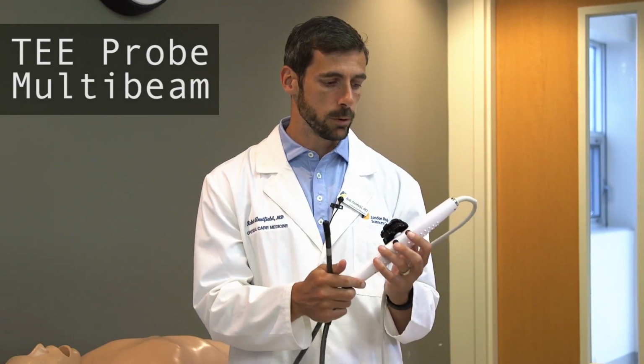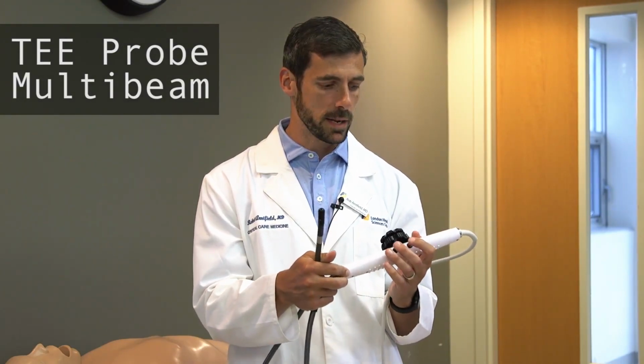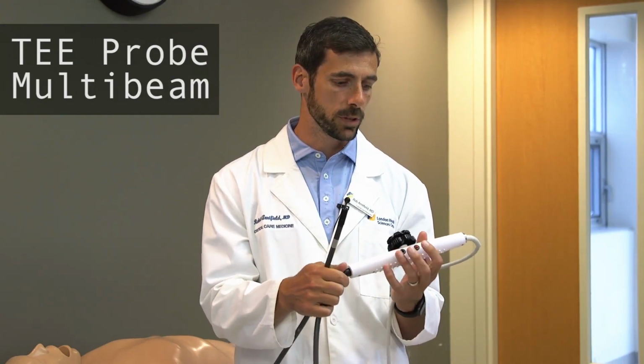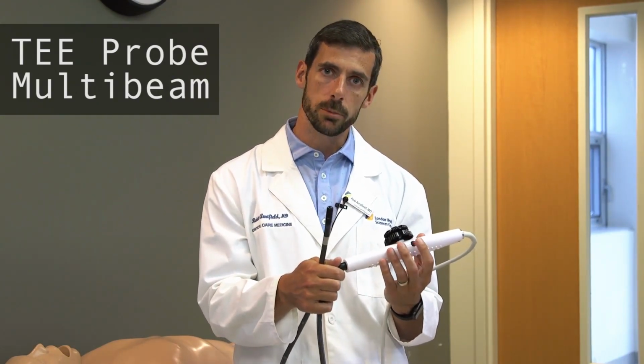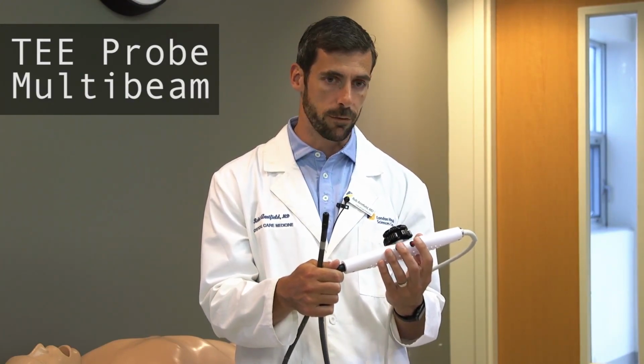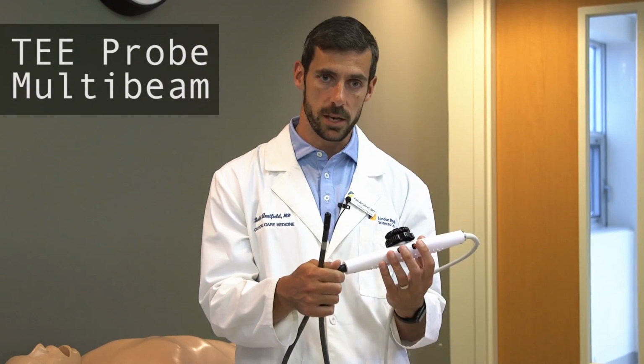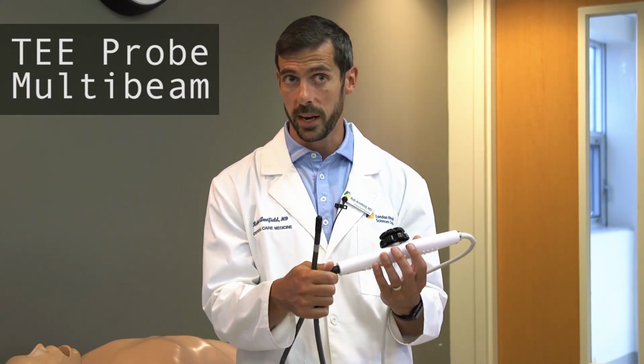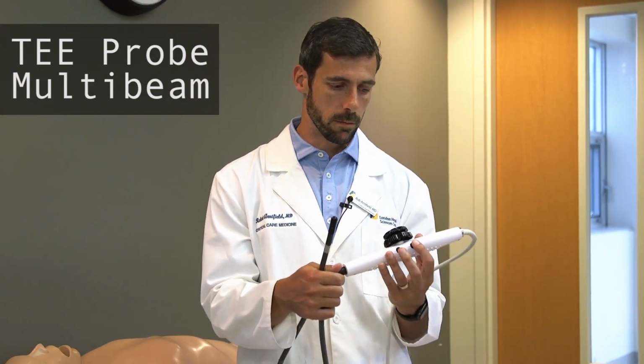Lastly, and perhaps most importantly, TEE is enabled in a multi-beam fashion by two buttons on the transducer handle, which control the angle of the ultrasound beam. We'll see this on the simulator momentarily, but ultimately toggling between different probe angles or multi-beam angles is afforded by the different buttons here. Typically the lower button will increase the angle from 0 up to 180, and the top button will decrease the angle from the position you're at.